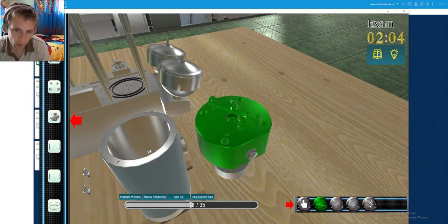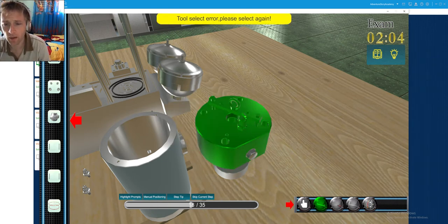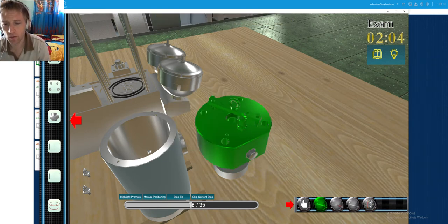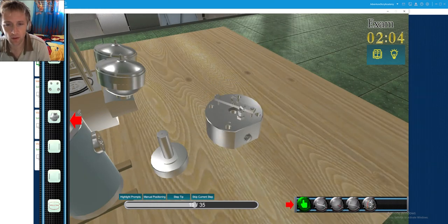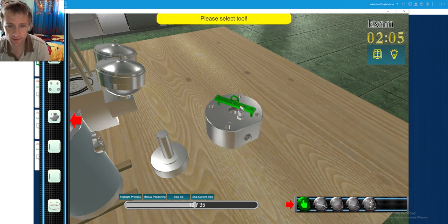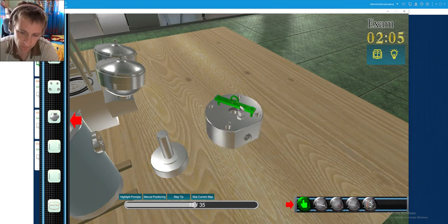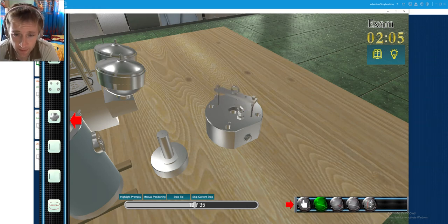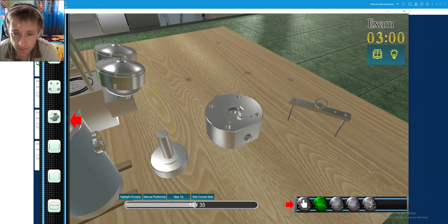In one vessel I remember which I was working as apprentice engineer, what we did, we removed the cylinder, the fuel pumps top covers and we replaced them because MAN changed the design and they had found some kind of damages. Some pieces were broken and entering the fuel line.